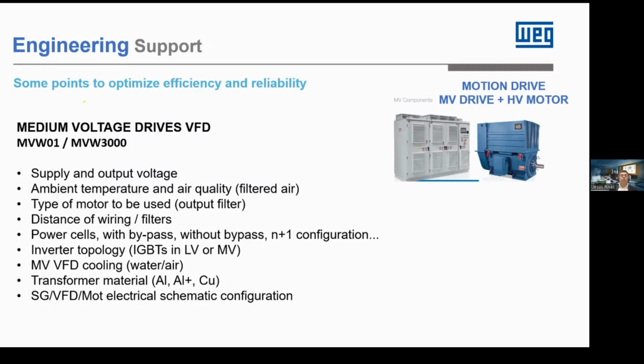We are also going to look at the different drive topologies. There are two topologies in the market, the cascade topology and the central point topology. The difference is whether the inverters, the IGBTs, are going to be in medium voltage or low voltage. We have the MVW01 model with the medium voltage IGBTs, and the MVW3000, which is more common in the water segment, with the low voltage IGBTs. We are also looking at the cooling system of the drive. Normally it's air, but it could be other special types like water. We have sold some water-cooled VFDs.